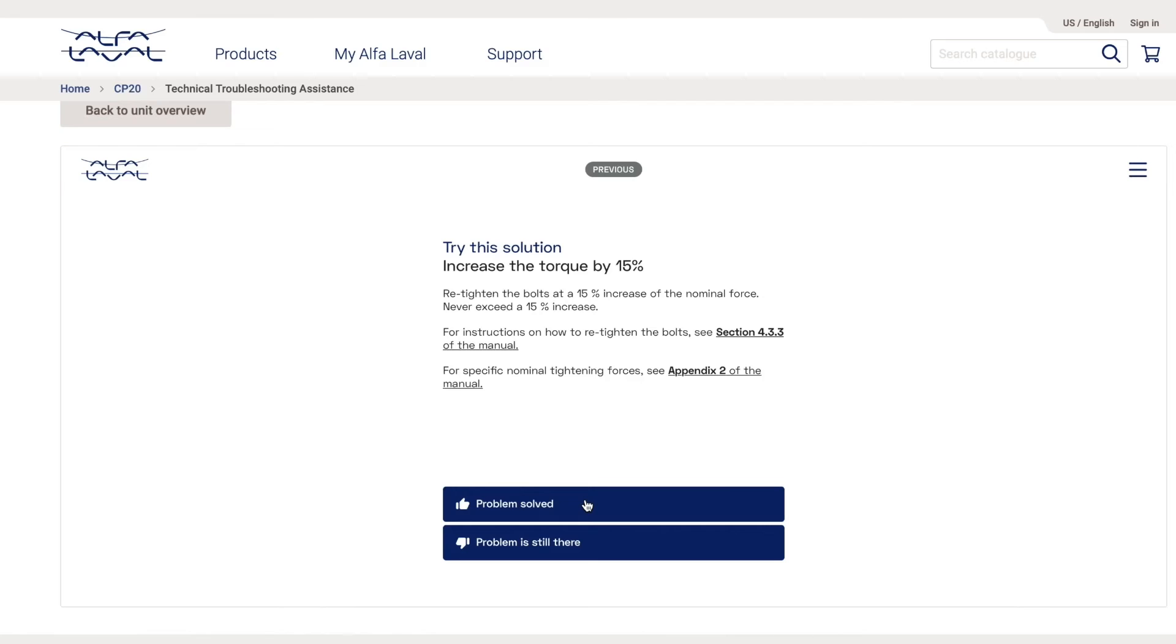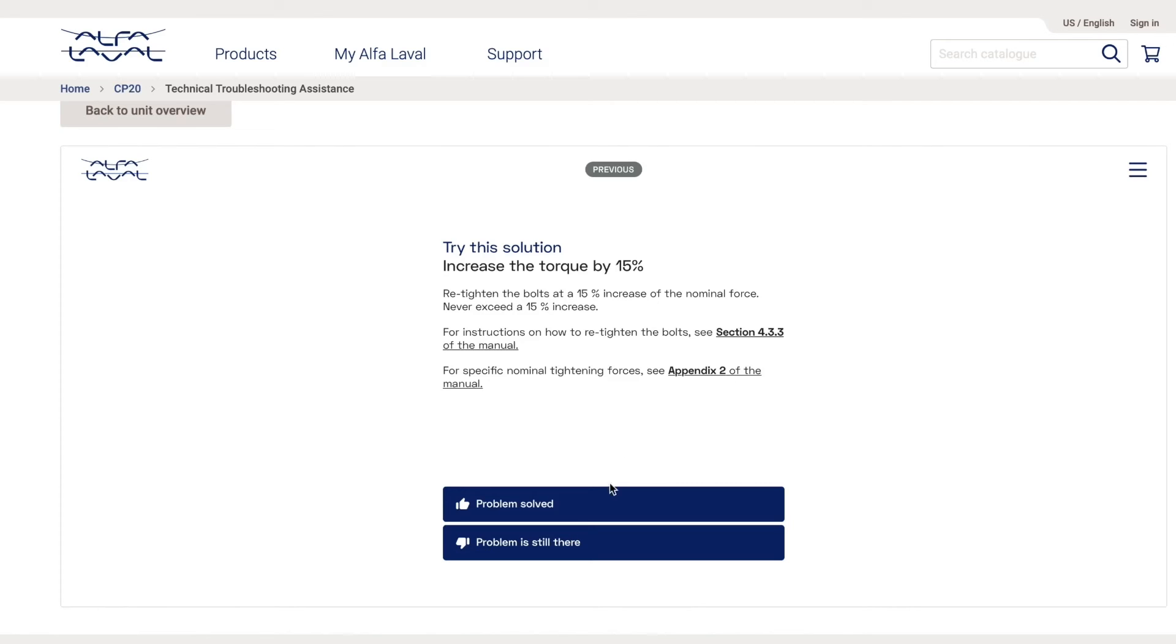I then can try this first suggested solution: increase the torque by 15%. Again, I can open the instruction manual and check the instructions on how to re-tighten the bolt. Let's say I did that. I increased the torque by 15% and the leakage stopped. So my problem is solved.